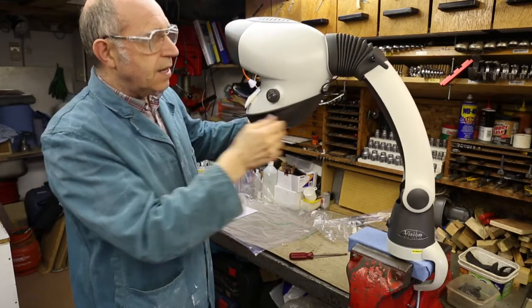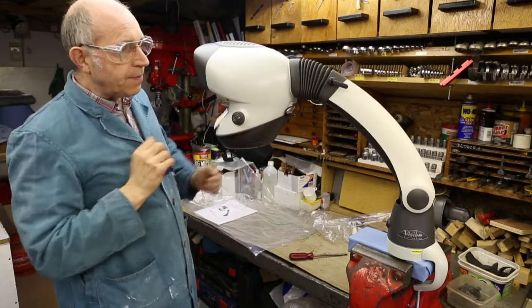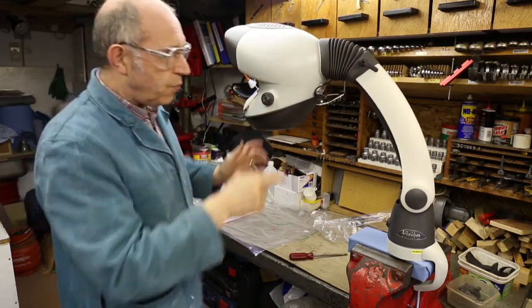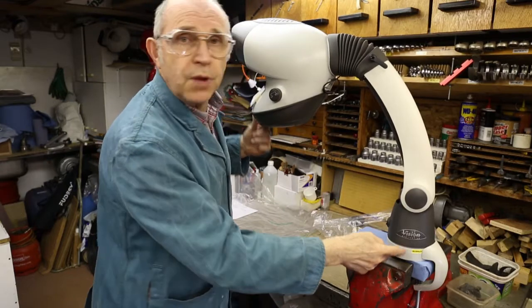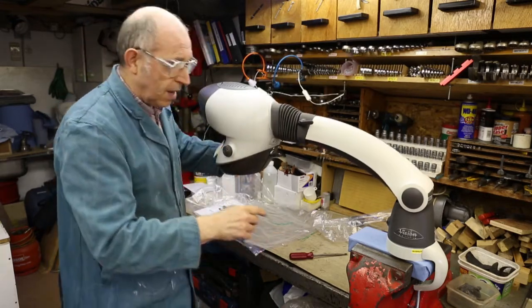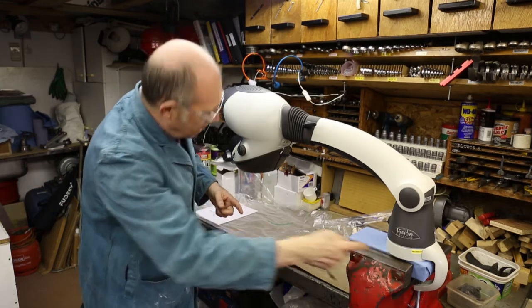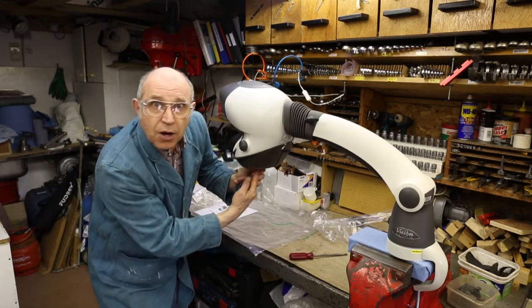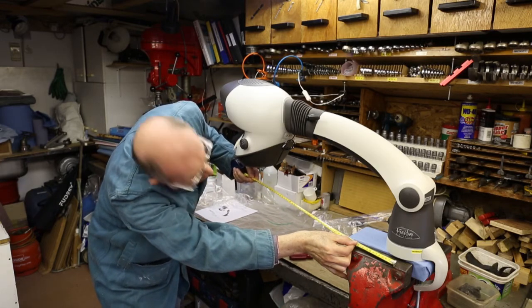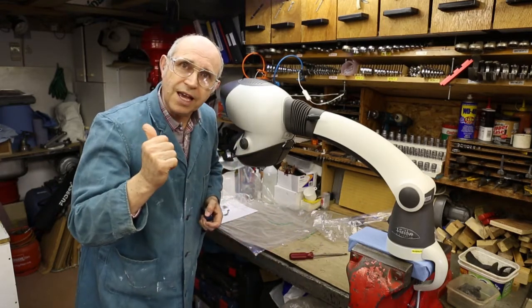This stand is a counterbalance stand - there's actually a spring in here which counteracts the weight of the head, so no matter where you put the head it stays and doesn't move. The reason we put this together is so I can measure the distance between the center of rotation of the stand and the center of the objective lens when this comes down to roughly the working height. I need to know the distance between the center here and the center of the objective lens. Measuring that, it comes to 590 millimeters. So that is the dimension I need when I work on the desk.